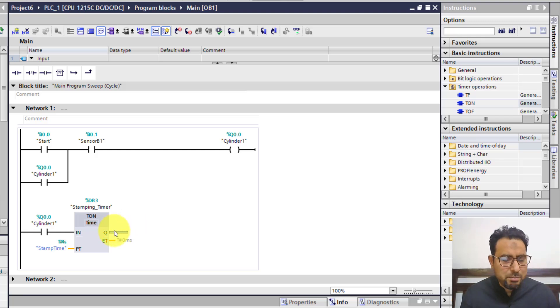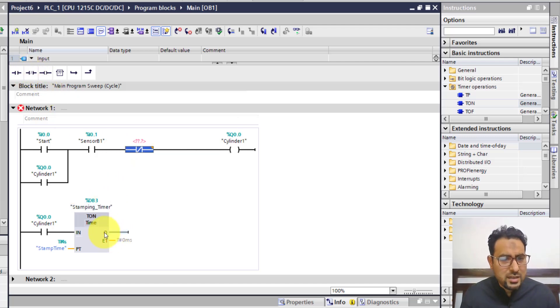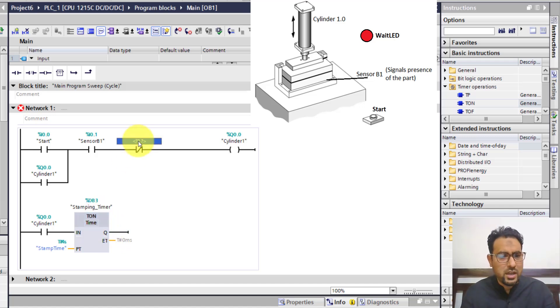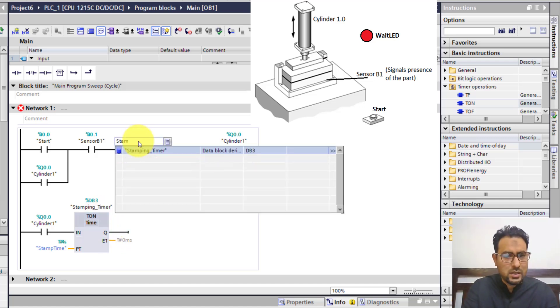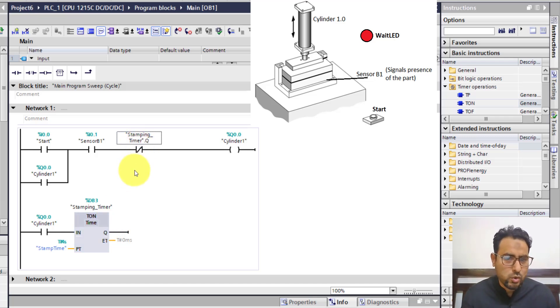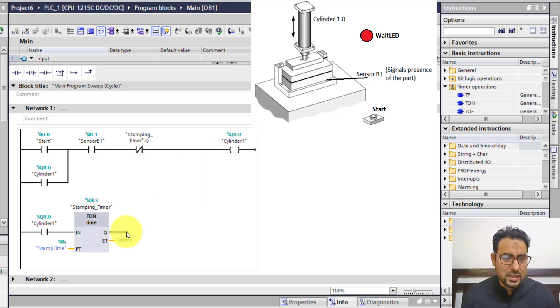If the timer is complete, I want the cylinder to turn off. So in this rung I need the Q-bit — the done bit — of the stamping timer. Using stamping timer's Q-bit, when this timer is done, the normally closed switch will open and the cylinder will turn off. Another thing I need is to count one when this timer has finished timing, which will signify that one part has been processed.